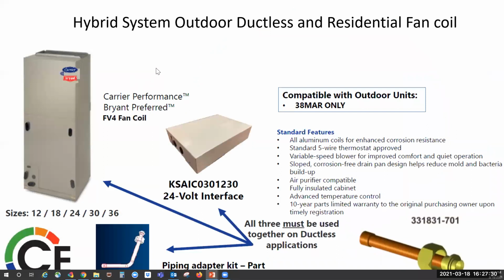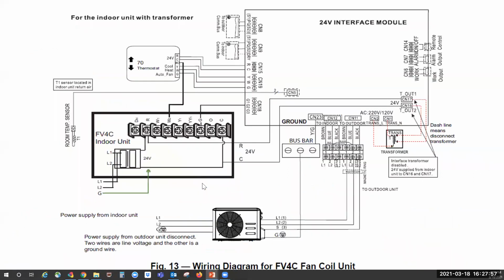Now, when we get into the hybrid systems, these are only compatible with the 38 MARs. You will have to remove the TXV, and you have one of two piping choices here and their numbers. You'll also have to install a 24-volt interface kit, and you will follow the interface kit per the installation manual.